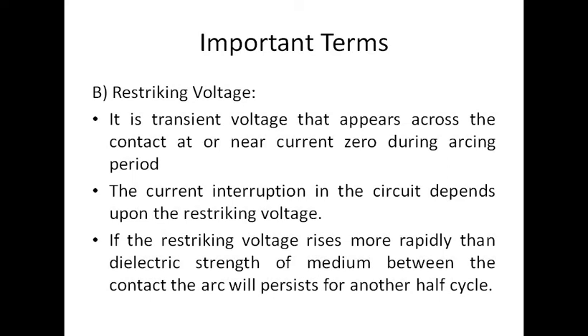The second term is restriking voltage. In the circuit breaker, when the arc forms between the moving contacts, we insert some medium to increase the dielectric strength, with the objective to extinguish the arc. If at any point the dielectric strength goes to zero, the arc is again restruck. At that instant, whatever voltage appears across the arc is known as the restriking voltage.